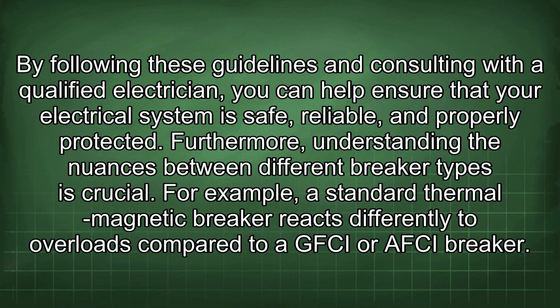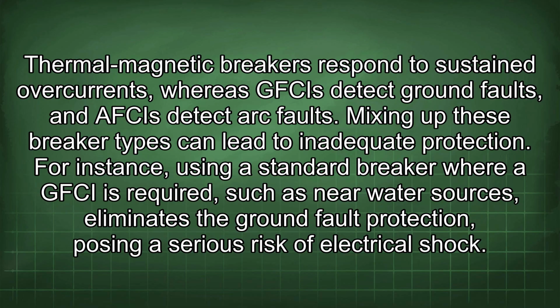For example, a standard thermomagnetic breaker reacts differently to overloads compared to a GFCI or AFCI breaker. Thermomagnetic breakers respond to sustained overcurrents, whereas GFCIs detect ground faults and AFCIs detect arc faults. Mixing up these breaker types can lead to inadequate protection. For instance, using a standard breaker where GFCI is required, such as near water sources, eliminates the ground fault protection, posing a serious risk of electrical shock.